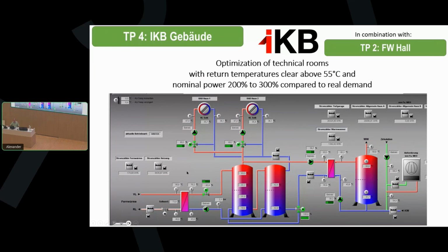And also, as you can see here, the heat substation of district heating to the building is dimensioned 200 to 300% more than necessary, which makes it inefficient because the physics does not work, and it makes it expensive because for each kilowatt you are connected with, you have to pay. In Austria, something around 20 to 100 euros per kilowatt per year.